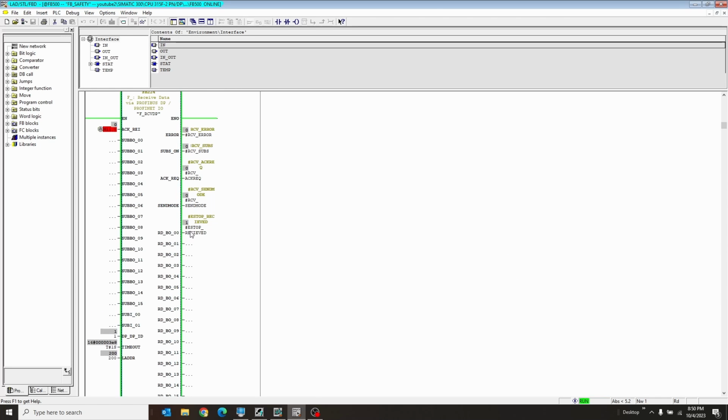The first bit here is the e-stop received bit, and he is high because the send on the other PLC is high. If I push the e-stop on the other PLC, that goes low. If I reset the other PLC, it goes high again because they're talking safety-wise to each other. So that's a safety-ready signal between two PLCs between a PNPN coupler. Super cool. And quite common.